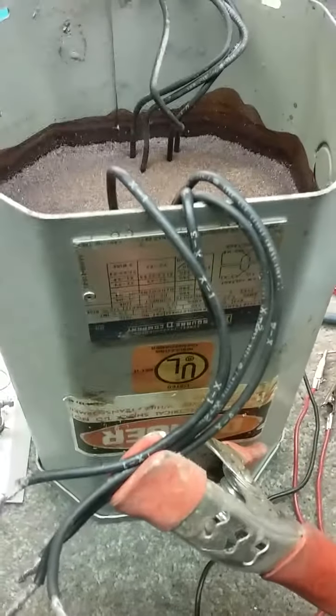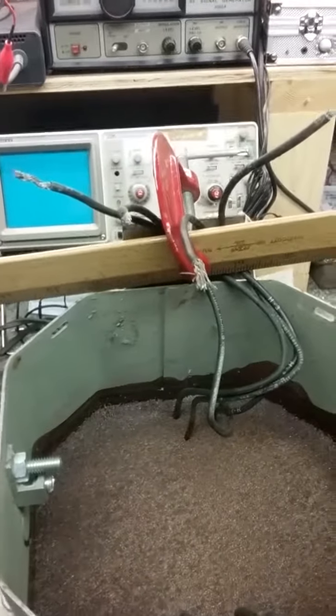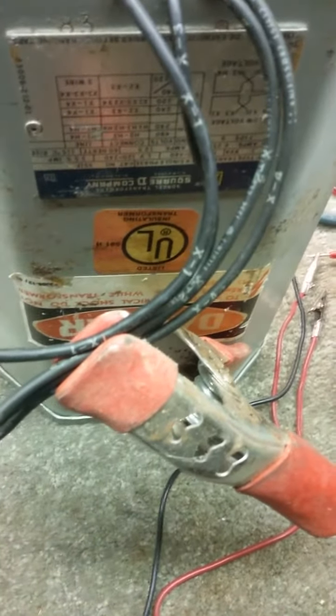Okay, the next thing we want to check is voltage in versus voltage out. This is a dangerous, you see the danger down there? This is a dangerous transformer. It draws a lot of current. It will kill you in a heartbeat if you don't know what you're doing. So if you do test something like this, make sure you know what you're doing. You can see that I'm using a ruler here to hold the wires apart with a metal clamp. Big no-no, right? And down here, a clamp with a wire almost popping out of it now. And those wires could short out at any time, right? Big risk of danger here.